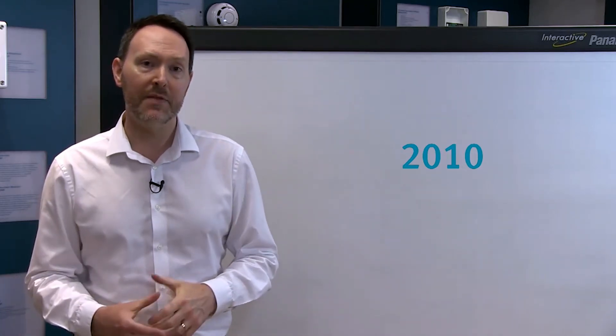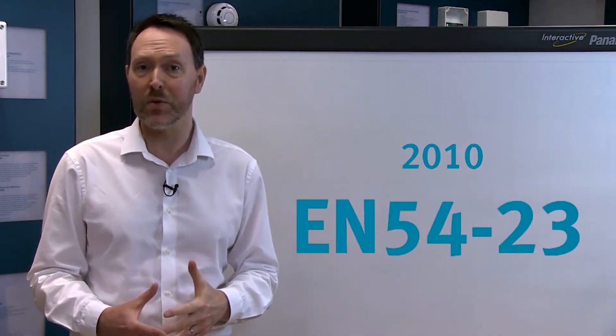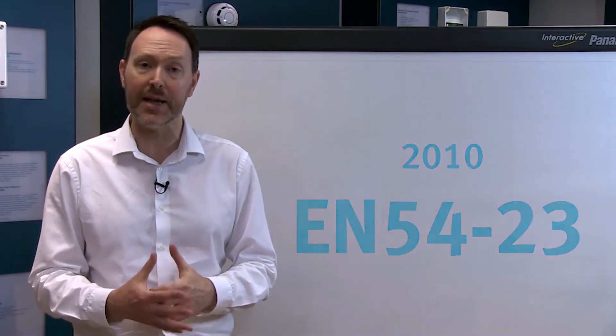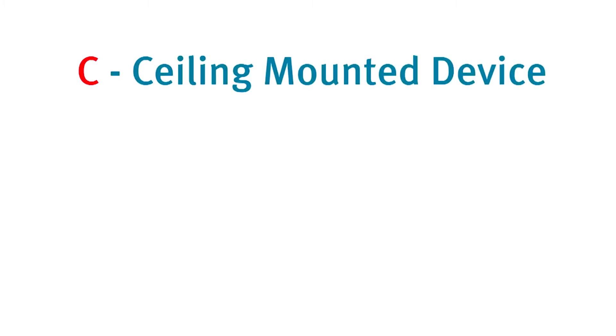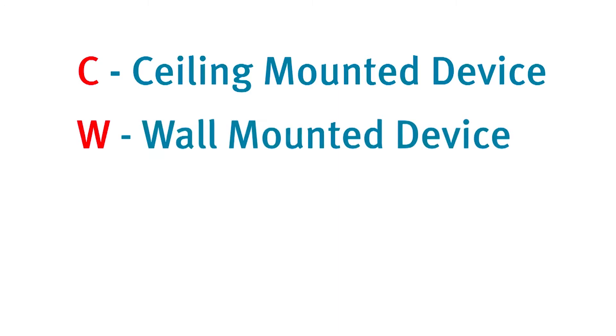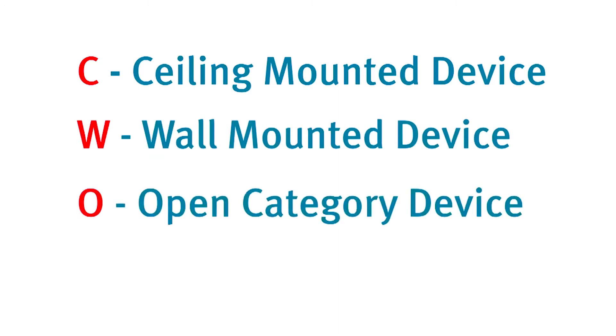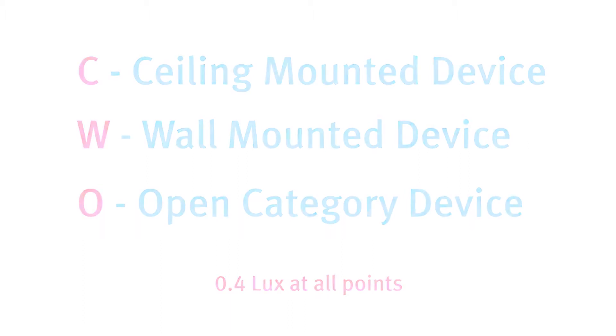Prior to 2010 there was no industry standard to determine the light output that a VAD should emit. Therefore EN54 part 23 was introduced to standardize the light output requirement. There are now three categories that a VAD can be rated under: C for ceiling mounted device, W for wall mounted device, and O for open category device. The specified output for a VAD is now required to be 0.4 lux at all points within the specified coverage volume, and all manufacturers are now required to label their VADs in a specific way.